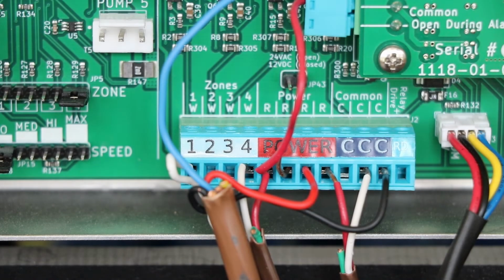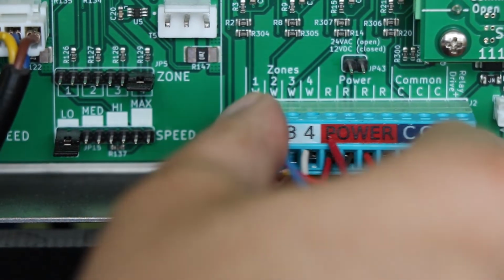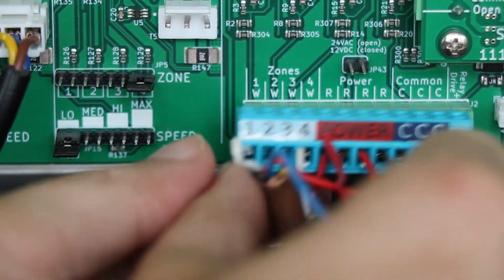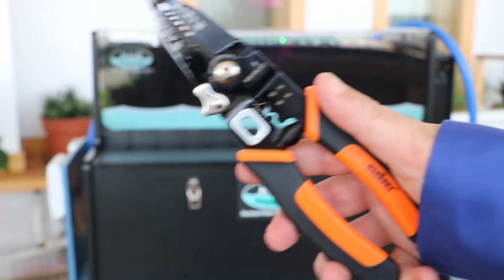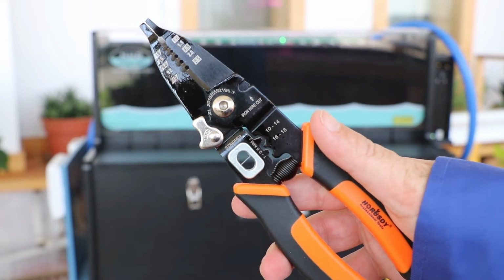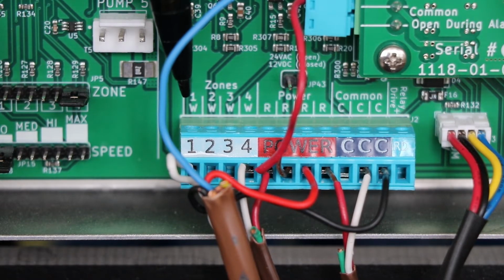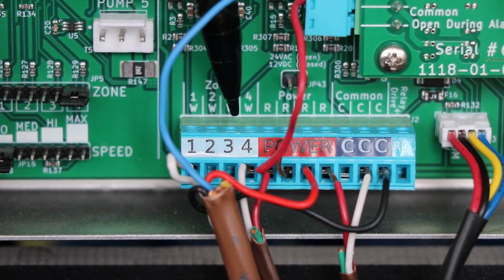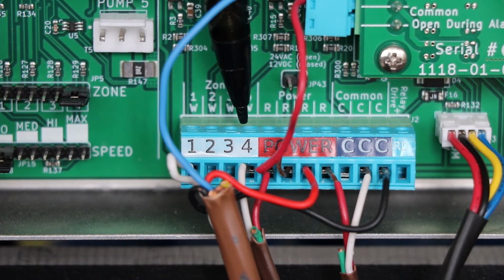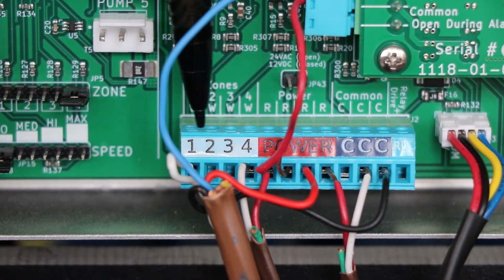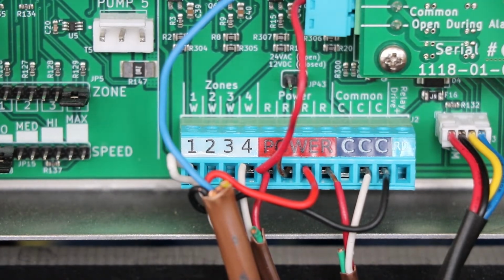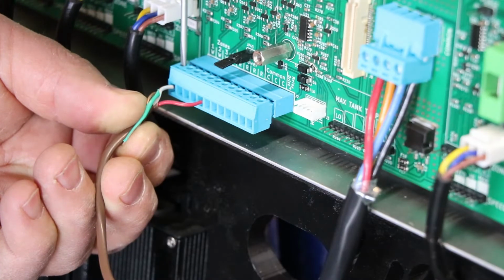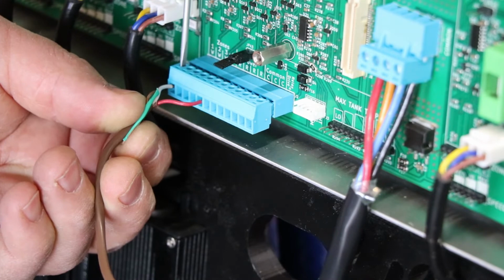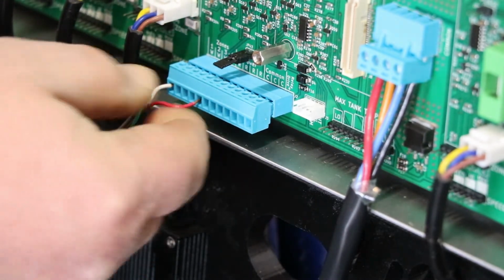Next, gently pull out the 12-pin wire connector from the bottom center of the control board. For each thermostat, we're going to connect the wires. Strip the end of the thermostat wires. If you have one, stick the white wire in the connector for the appropriate thermostat zone number. Then, tighten the little screw and turn to the right, as tight as it will easily go. This should hold the wire securely and make the electrical connection possible.